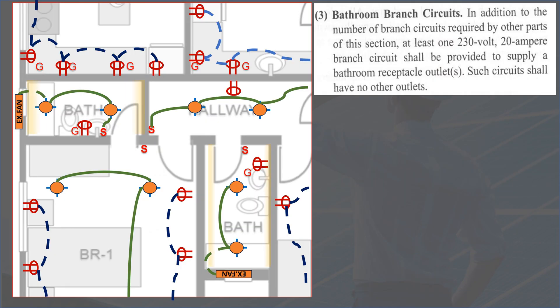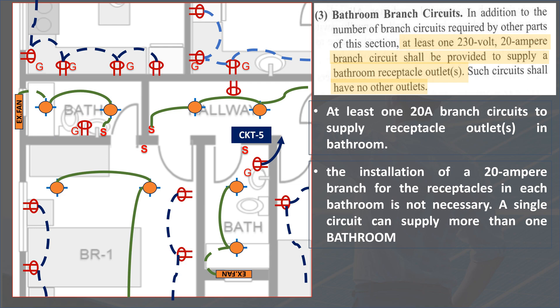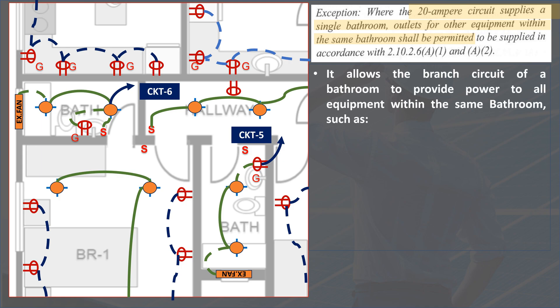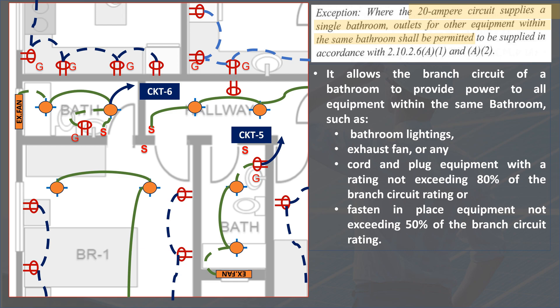For branch circuit requirements for the bathroom, paragraph 3 of the same section states that in addition to the number of branch circuits required by other parts of this section, at least one 230V, 20A branch circuit shall be provided to supply bathroom receptacle outlets, and such circuits shall have no other outlets. The bathroom must have at least one 20A branch circuit to supply receptacle outlets. A single circuit can supply more than one bathroom. Exception: where the 20A circuit supplies a single bathroom, outlets for other equipment within the same bathroom — such as bathroom lighting, exhaust fan, or cord and plug equipment not exceeding 80% of the branch circuit rating, or fasten-in-place equipment not exceeding 50% of the branch circuit rating — shall be permitted.